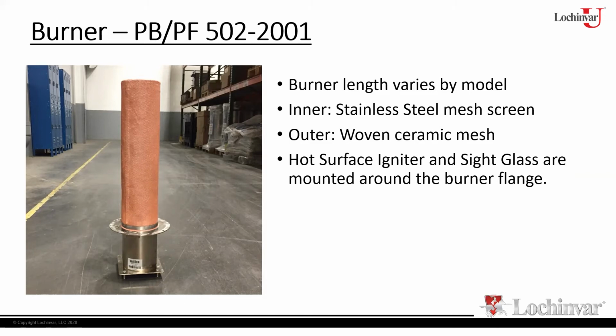The burner is kind of unique because it's kind of soft. If you grab the burner, you can actually squeeze that mesh. You can bang it across the table and won't damage it, so you can do different things with it at that point. Now the kicker with this is, same with any burner, if there's physical damage to the burner, to the mesh, then at that point the burner would have to be replaced.